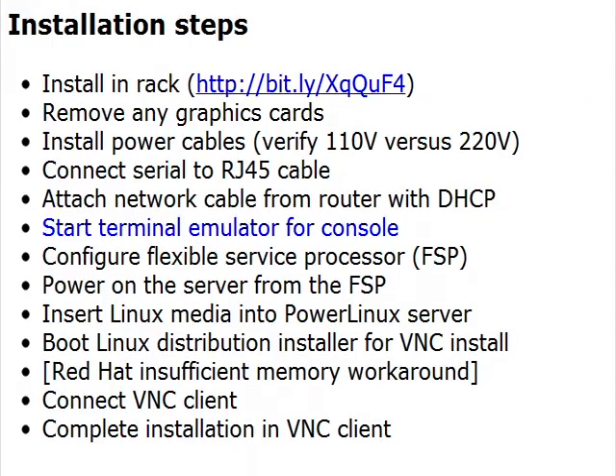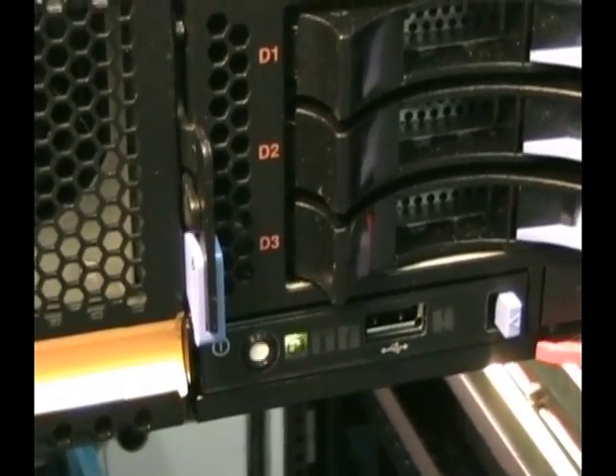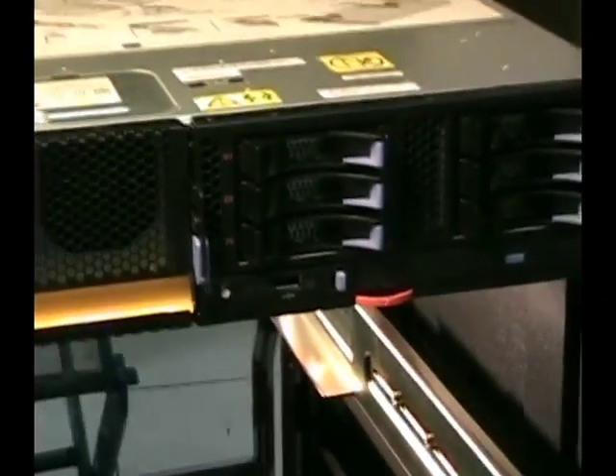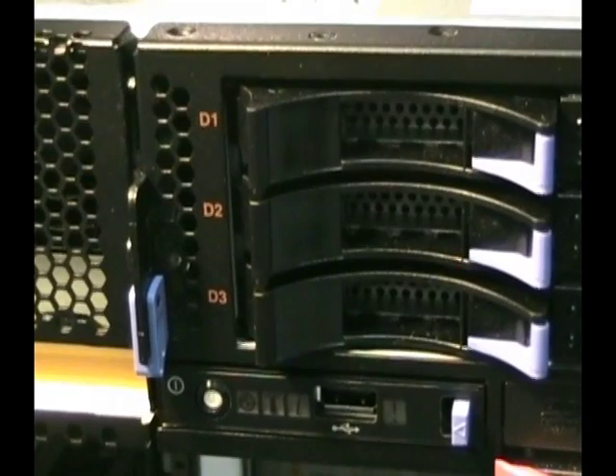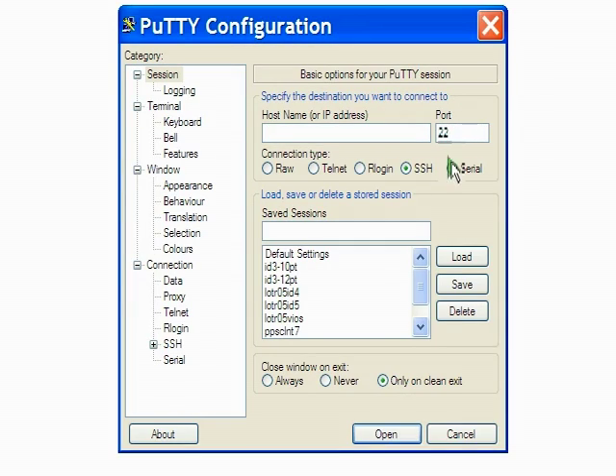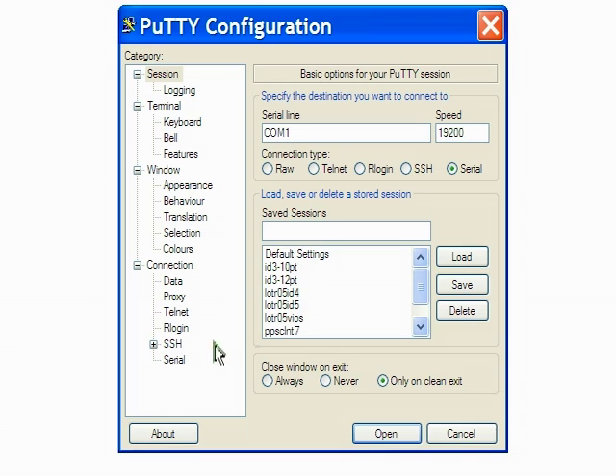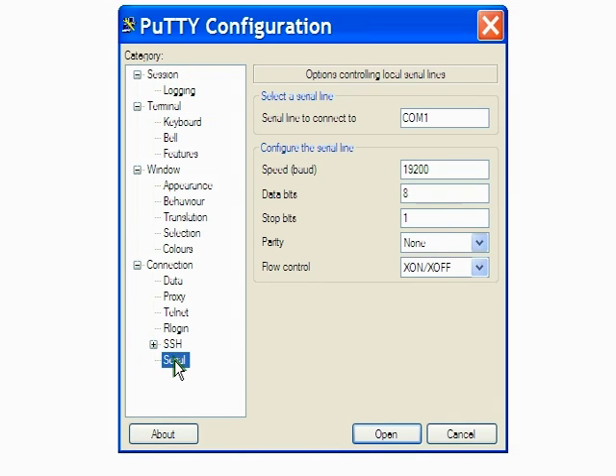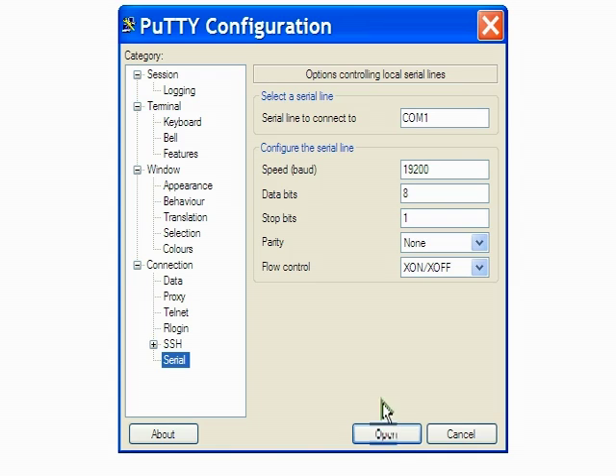Now it's time to set up the terminal emulator for the console. First, verify that the green power LED on the control panel is flashing. Configure the serial console emulator application for a speed of 19,200 bits per second with eight data bits, one stop bit, and no parity. If the application is running on Windows, specify the COM port associated with the serial port of the PC, which is most likely COM1. Finally, start the console.